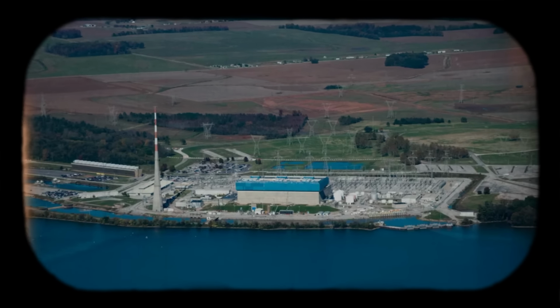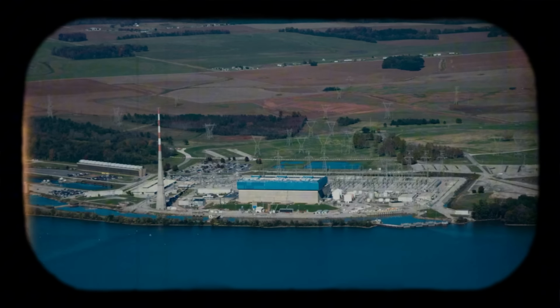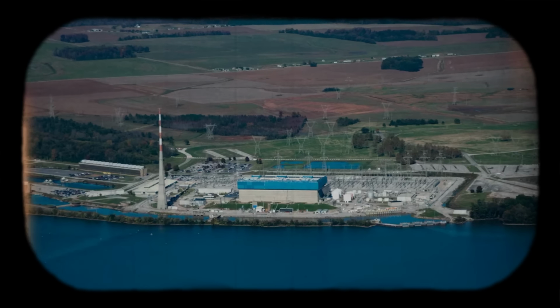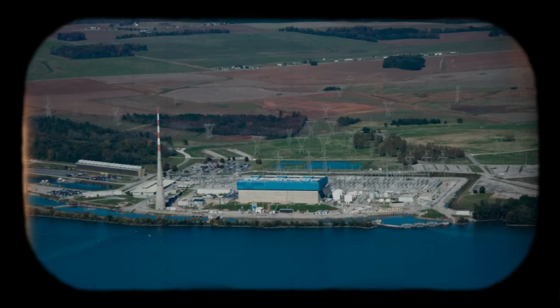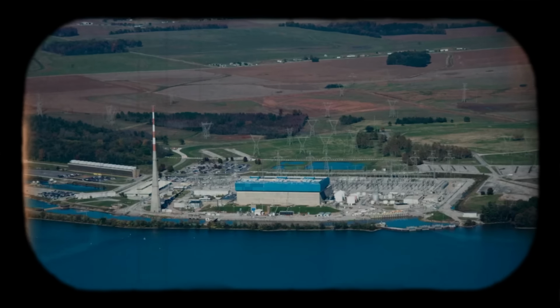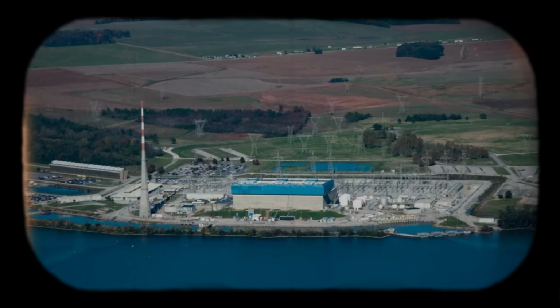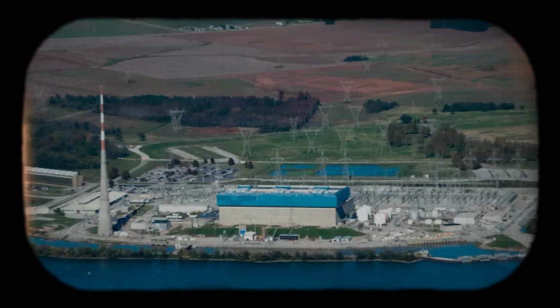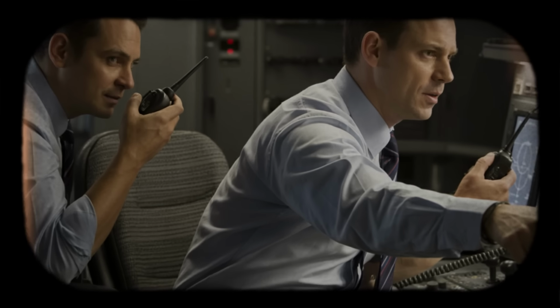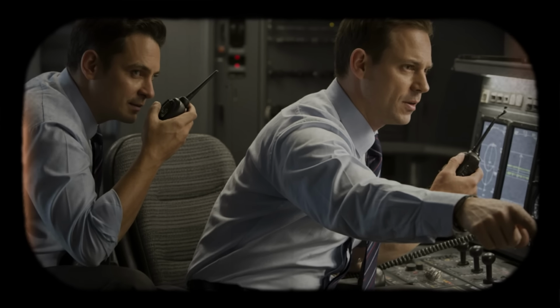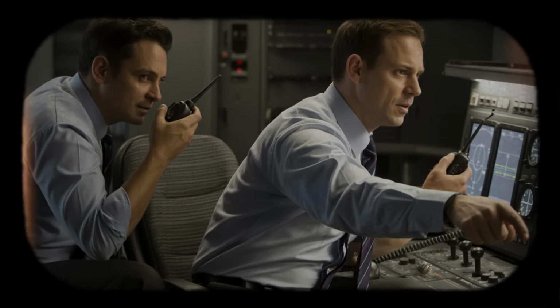1:10 to 1:20 in the afternoon. Units 1 and 2 control rooms. Operators observe erratic signals from emergency core cooling system instrumentation. The ECCS is designed to remain reliable through diverse routing: physical separation of cable runs, different power supplies, independent instrument channels. But multiple circuits are now showing degraded or intermittent behavior.